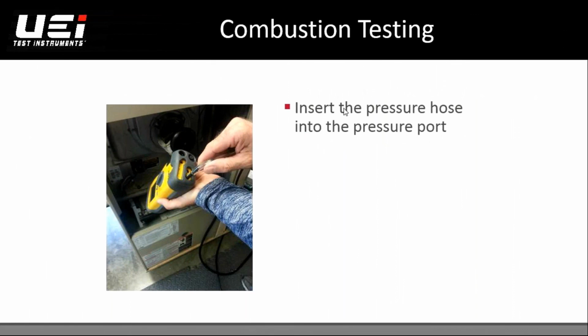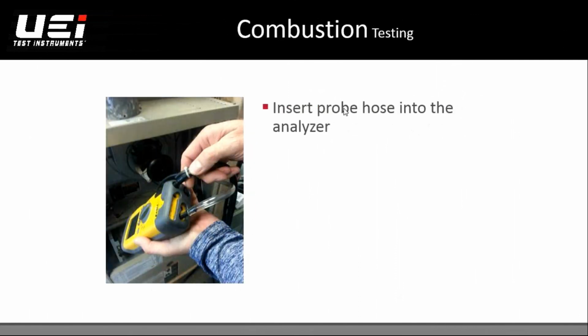I talked earlier about the probe, and that probe has two parts. One part is a pressure hose that you're going to put into the port. On the higher end models, you'll see that it'll have a P1 and P2, so you can do differential pressures. Then you're going to insert the probe into what they call the water trap - remember we talked about H2O being a byproduct of the combustion process - so you want to make sure that you plug that in there.